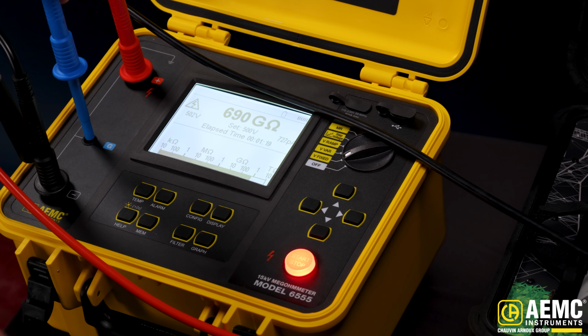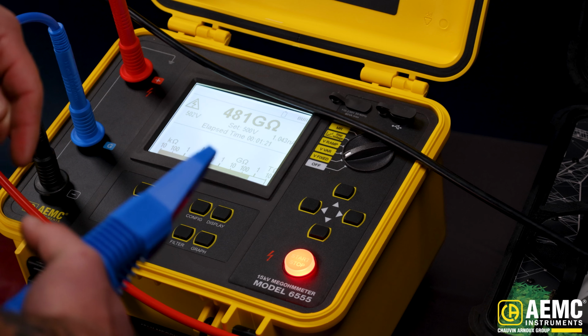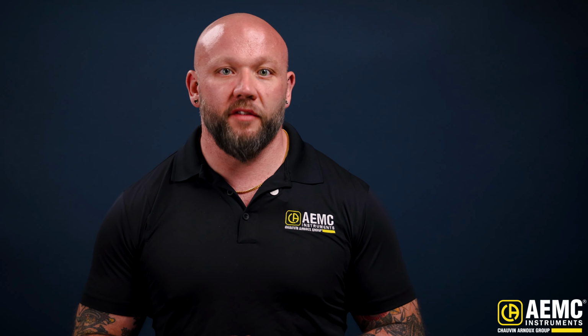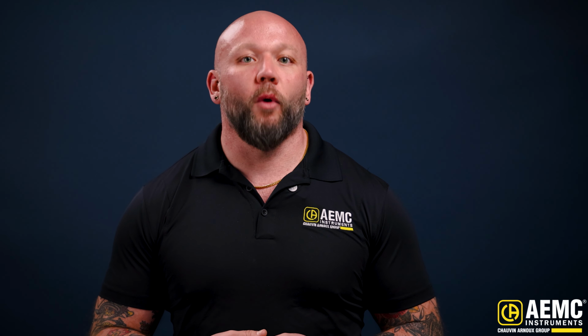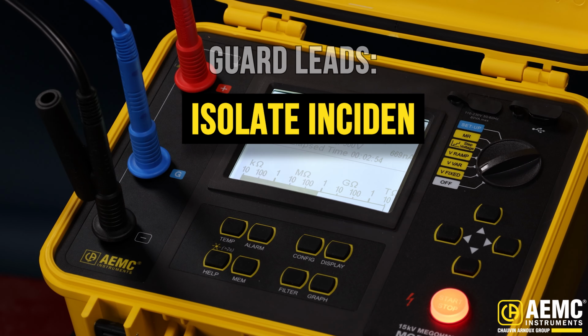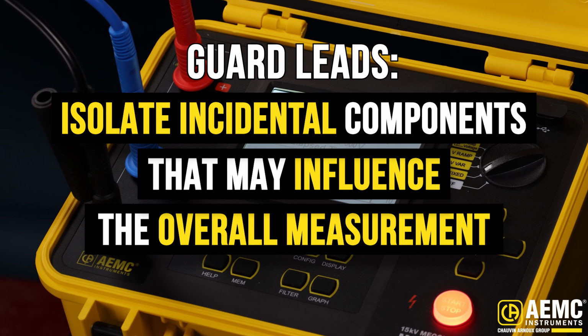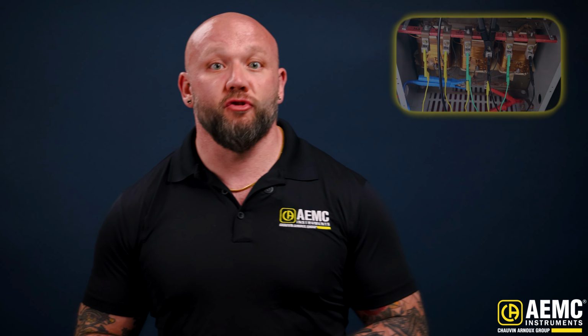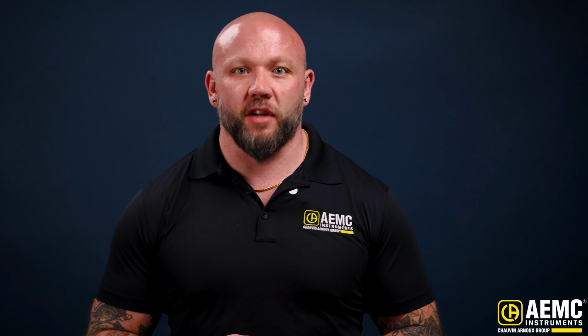The guard terminal is a simple but useful feature that shunts unwanted leakage currents away from the measurement. In short, it gives you a more accurate reading of the actual insulation resistance by isolating incidental components that may influence the overall measurement. Let's break it down with a real example using a three-phase dry-type transformer, which are commonly tested for insulation resistance because they're often exposed to contamination in the open environment.